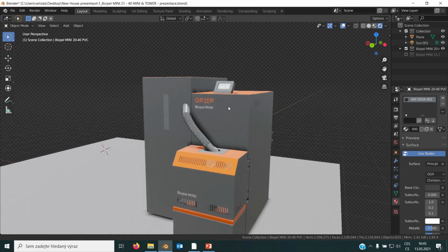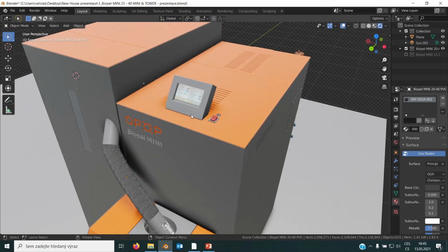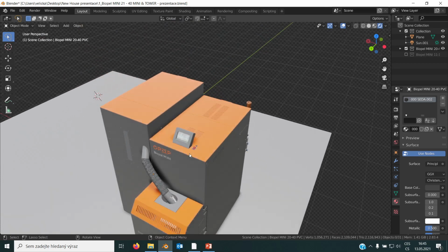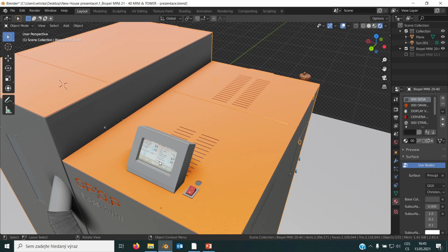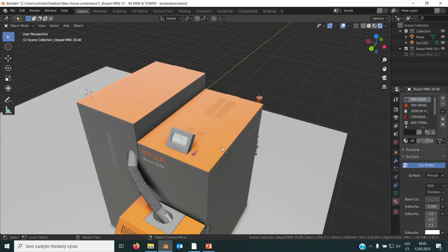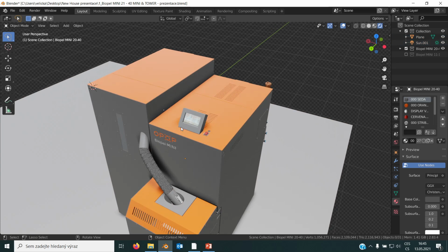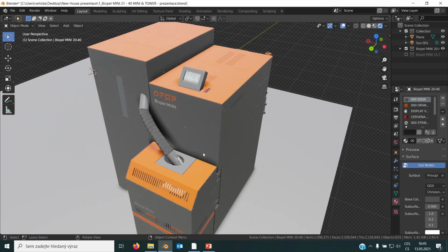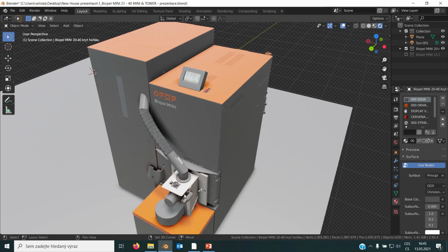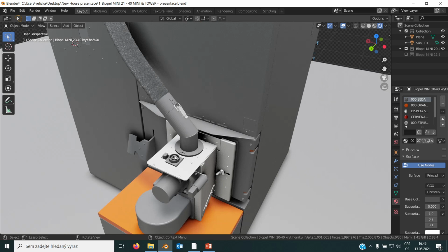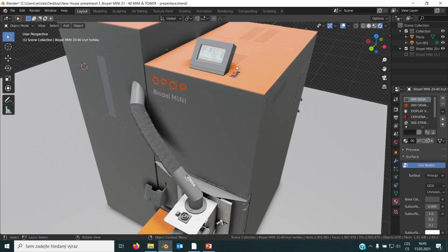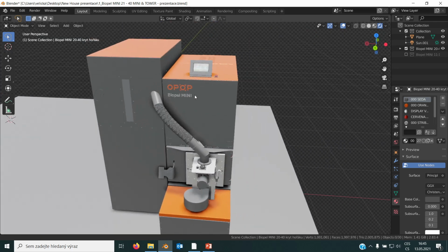Speaking of cabling, when you receive the boiler, you install the display. The display will be hidden inside the ash container, so you just, with 2 screws, install the display on the top. And when you remove this orange cover on the top, below there is the main control unit, and there will be 2 cables. There will be a cable for the feeder, and there will be a cable for the burner, to connect the burner with the cable here. So again, it is not connected because you are the one who will decide where the pellet hopper will stand. If the pellet hopper stands on the left side, of course the cable for the feeder will go through the boiler to the pellet hopper on the left.